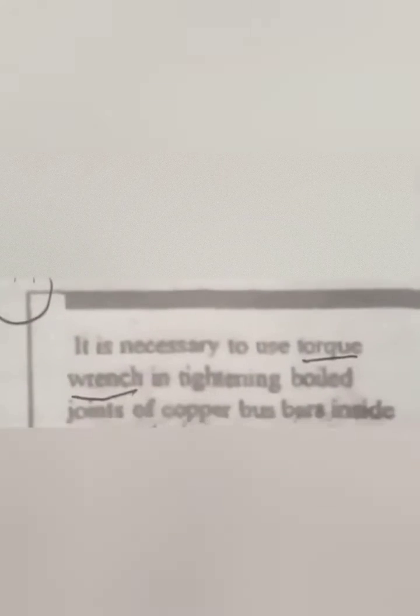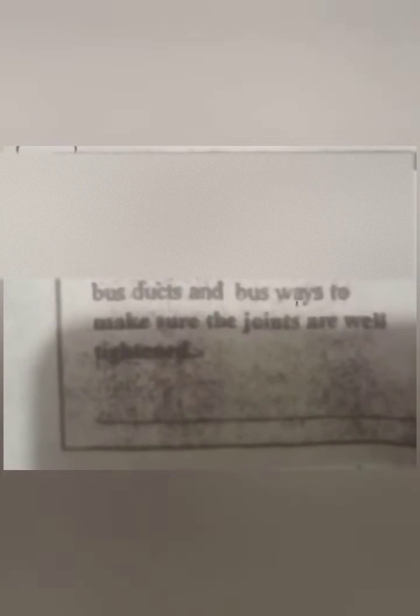Number 14. It is necessary to use a torque wrench in tightening bolt joints of copper bus bars inside bus ducts and busways to make sure the joints are well tightened.